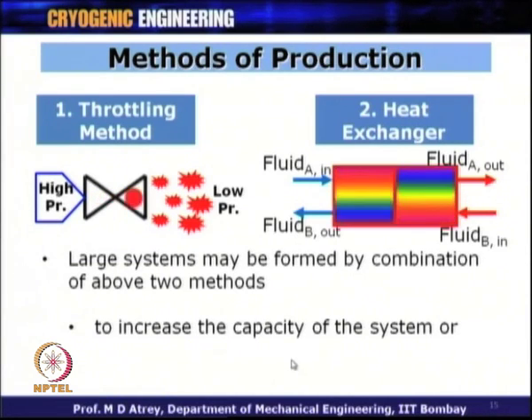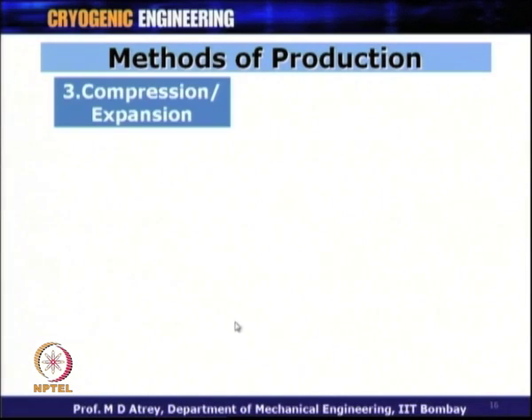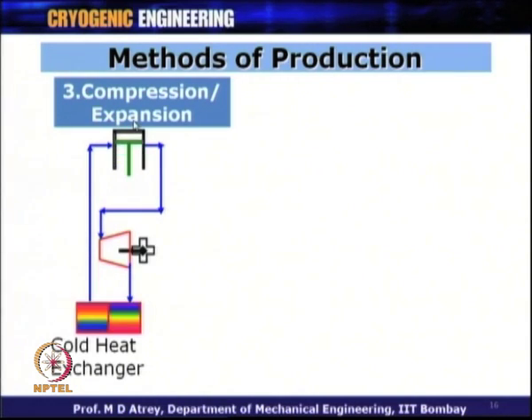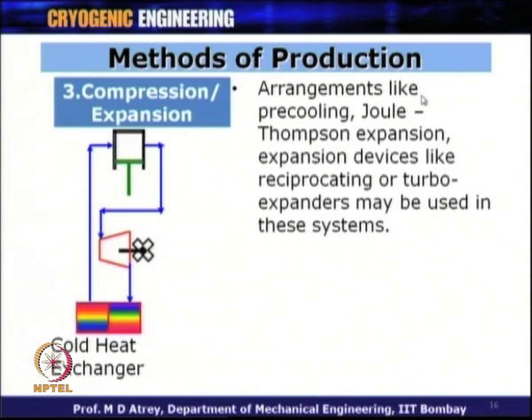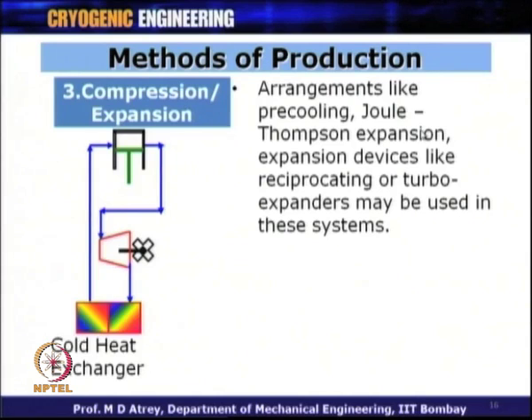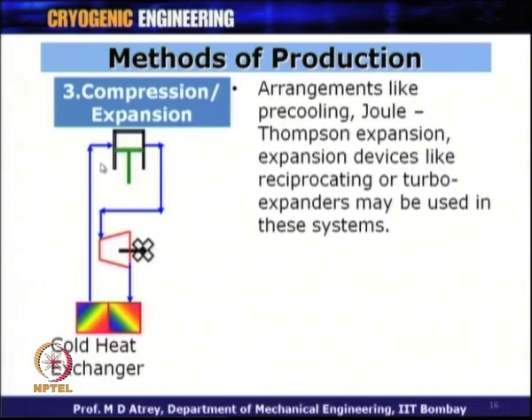Larger systems may combine multiple techniques — throttling, heat exchangers, and expansion devices — in the same circuit to increase capacity or reach very low temperatures. The third method is compression and expansion: gas is compressed to high pressure, then expanded in an expansion device to achieve lower temperature. This cold is then transferred via a heat exchanger. Arrangements like pre-cooling, Joule-Thompson expansion, and expansion devices such as reciprocating or turbo-expanders may all be used. COP and capacity can be improved by the proper choice of compressor, expansion device, and heat exchanger.